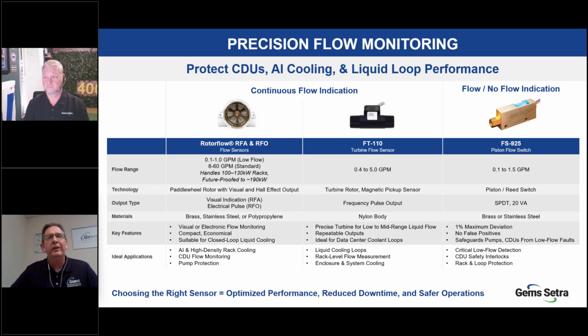Moving to the last piece of the puzzle, this is really a safety device, a flow or no flow. So the way it'll indicate is if you're at a certain flow rate or above for that setting, the switch is actuated. When it drops below, that switch will deactuate, telling you that you've lost flow and you may want to be doing something about it. So this is in brass or stainless steel. Being reed switch based, it's highly durable, highly repeatable, and again, for those critical low flow detection. So let's talk about how they work a little bit. Next slide, please.